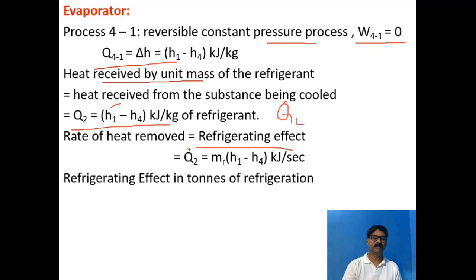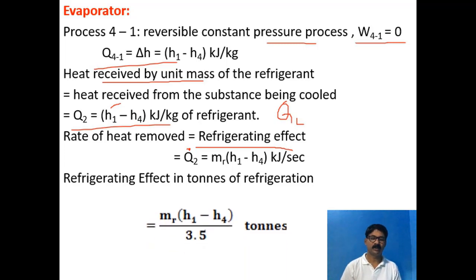If you want to calculate the refrigerating effect in tons of refrigeration, divide Q̇ᴸ = ṁᴿ × (H₁ − H₄) by 3.5, because 1 ton of refrigeration equals 3.5 kJ/s. Dividing by 3.5 gives the refrigerating effect in tons of refrigeration.